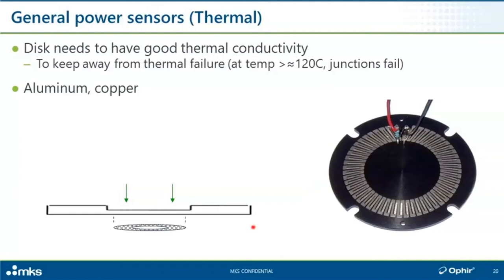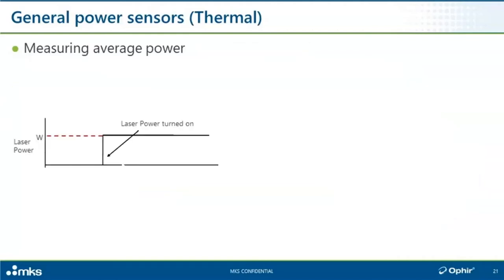There are a whole lot of design considerations. The disc material needs good thermal conductivity so the heat being produced can be removed as quickly as possible to make room for more. If heat comes in faster than it goes out, the temperature starts to rise, and at around 120°C the first point of failure would be a disconnect at one or several junctions — resulting in instant sensor death. For lower powers we make the discs out of aluminum; for higher powers we use copper, which has better thermal characteristics but is more expensive. We also have to make it thin. A lot of stuff goes into the design of these things.